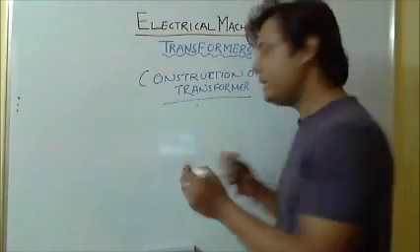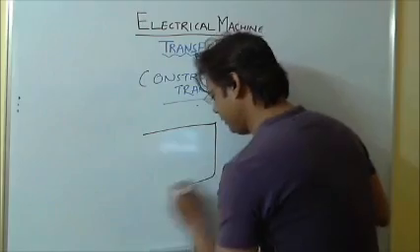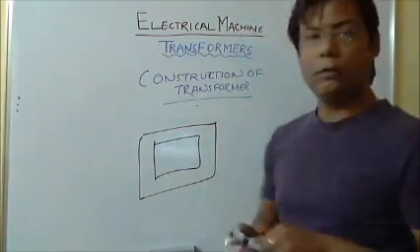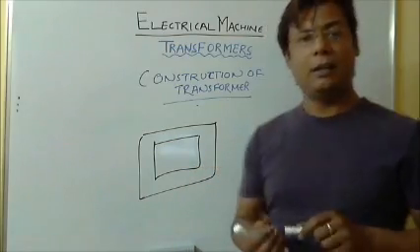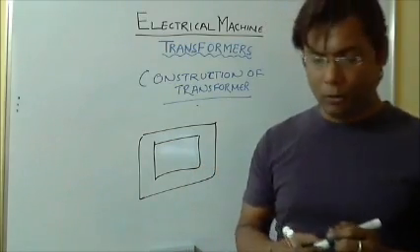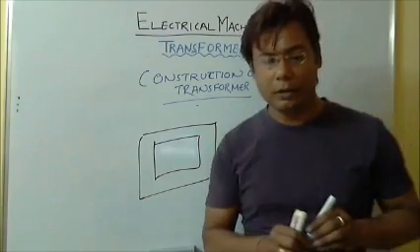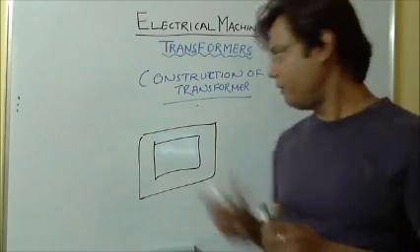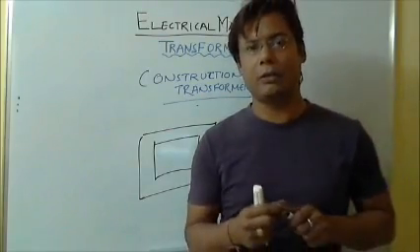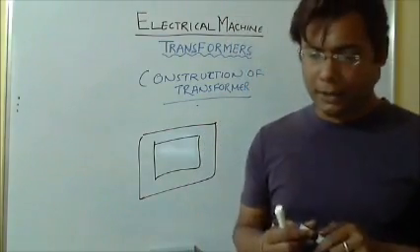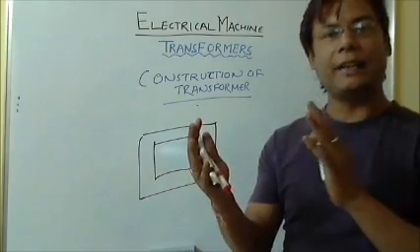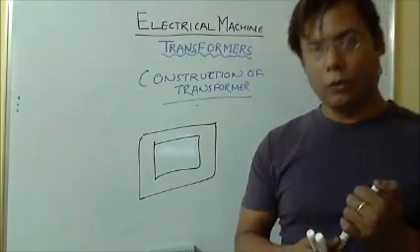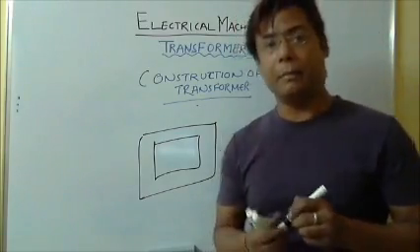There is a core. This core is normally made up of CRGO, that is called cold rolled grain oriented steel, which is maintained in such a direction that it will give minimum core losses as well as high permeability.